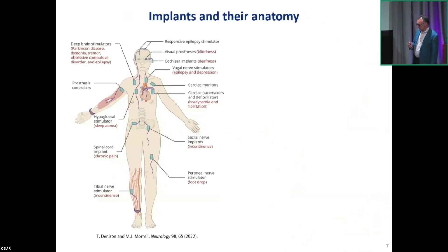This is a snapshot of the present different devices that are available, placed at different locations, with the indications that they treat here in red. And by and large, all devices look like this. There is a tin can that contains about 2/3 of the volume, the battery, and 1/3 electronics that create current pulses that are taken through these leads to electrode arrays that are placed in the location where intervention is needed.